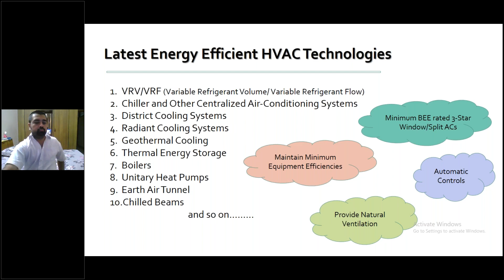Some of the technologies, like geothermal or radiant, are irrespective of refrigerant techniques. They are not using refrigerant, because we all know refrigerant directly impacts our environment, causing carbon emission and climate change impact. So we must depend upon evaporative cooling systems, geothermal or radiant cooling systems, or there is a provision where we are using VRV, chillers and district cooling. We need to integrate them with high COP, like more than 5.6 or 5.8 in chillers and more than 3.6 COP in VRF systems. So these are the major requirements which we need to use and focus on.